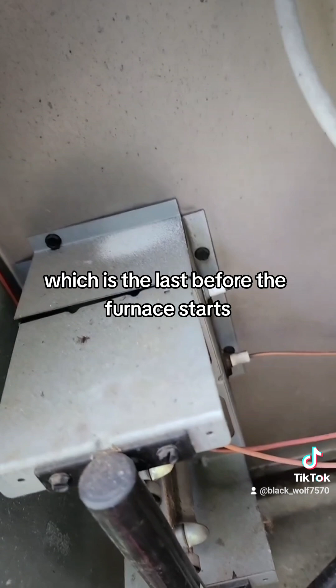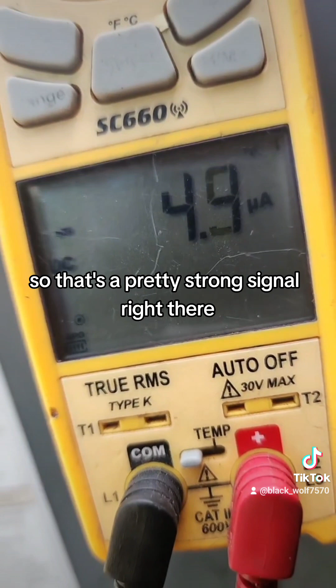Alright, so what I'm going to do now is I'm going to test that flame sensor right there, which is the last thing before the furnace starts. You see the furnace started, just kick off. Because I don't got the wire connected. So what I'm going to do is I'm going to make a connection with my meter. Pretty much it's coming in the red, coming out the black, and I should get a number here. So that's a pretty strong signal right there.